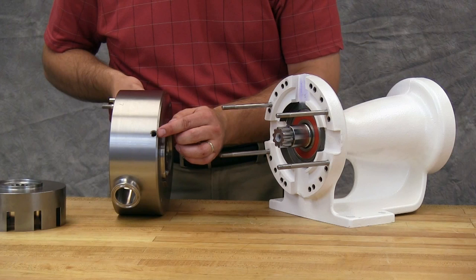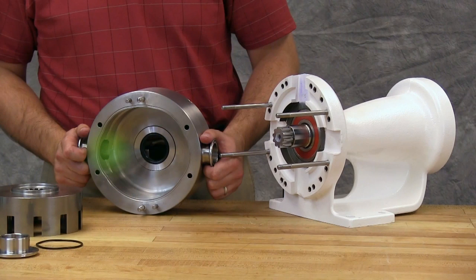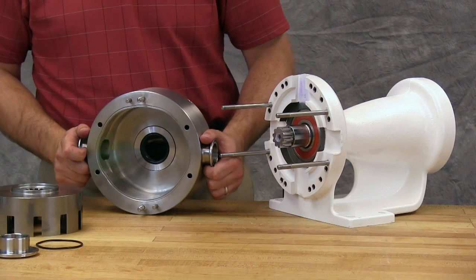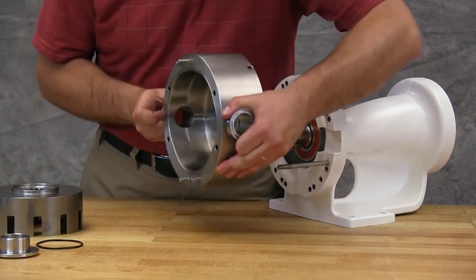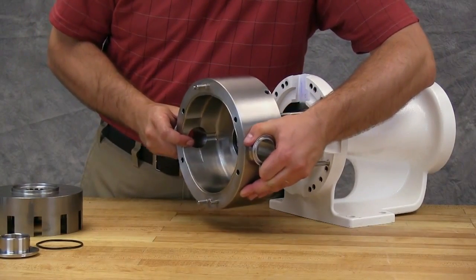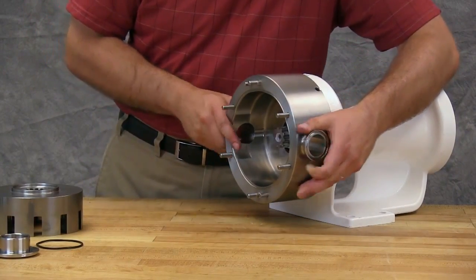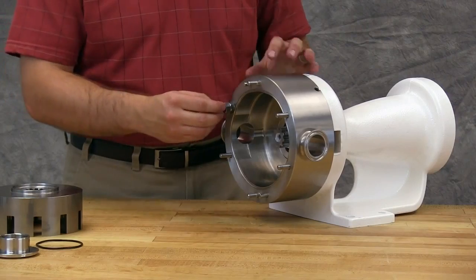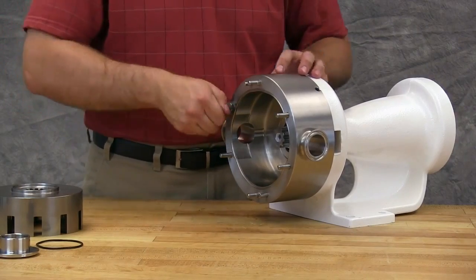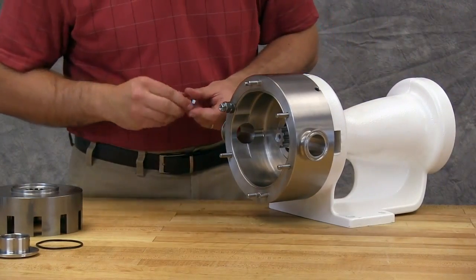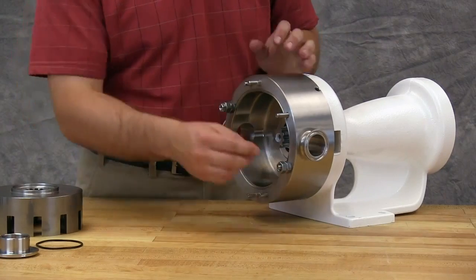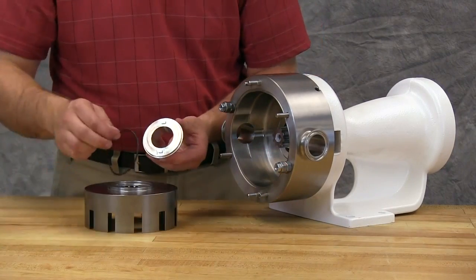For single seals, plug the barrier fluid connections with pipe plugs. The port with the casing groove needs to be used as the suction port for the pump's primary rotation. Use the casing studs to install the casing on the bracket. Use 2 nuts to hold the casing in place during assembly. It is important the casing is secured during assembly to avoid damage to the pump internals.